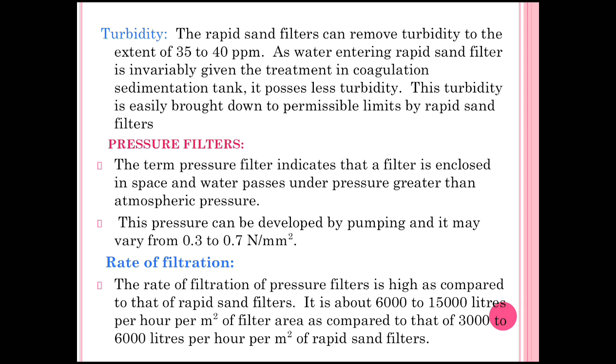Now the next is the pressure filters. The term pressure filter indicates that a filter is enclosed in space and water passes under the pressure greater than atmospheric pressure. This pressure can be developed by pumping and it may vary from 0.3 to 0.7 N per mm square.